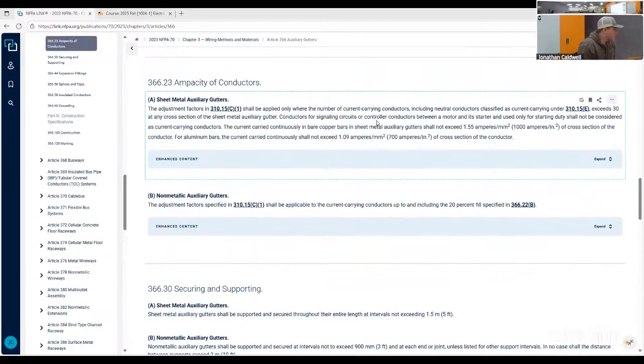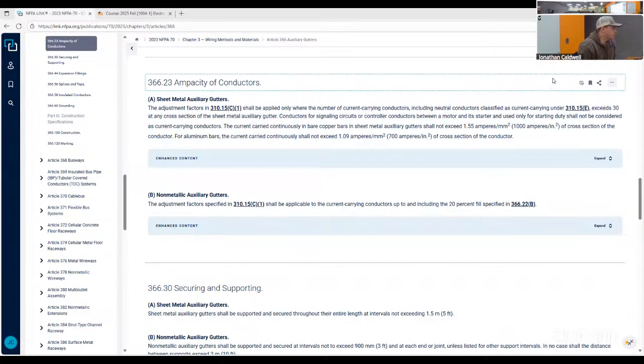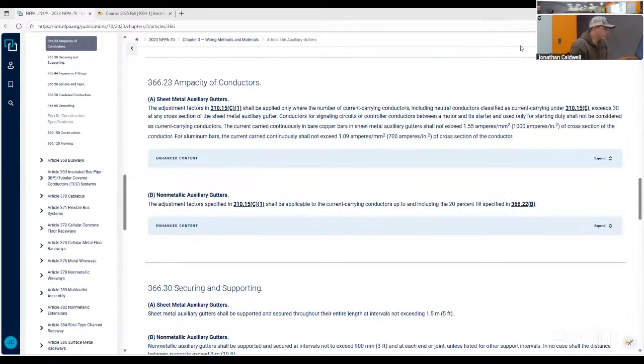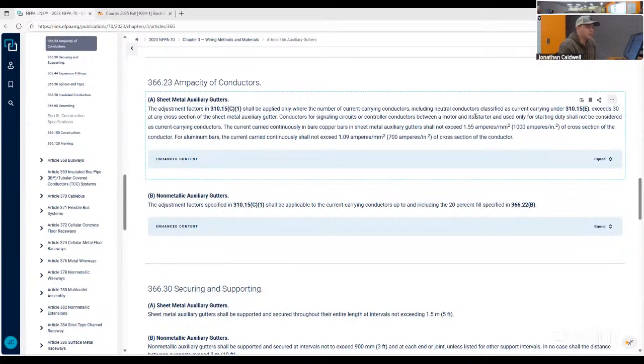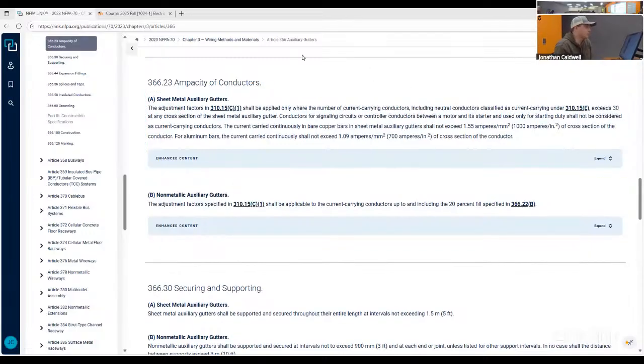So the adjustment factors in 310.15(C)(1) shall be applied only where the number of current carrying conductors, including neutral conductors classified as current carrying, exceeds 30 at any cross section of the sheet metal auxiliary gutter. Conductors for signaling circuits or controller conductors between a motor and its starter and used only for starting duty shall not be considered as current carrying conductors. So just real quick, signal circuits like fire alarm, things like that, and then a starter, a start-stop circuit. There's no other current going through it; the only current is when you push that start button, and that's the only time the current goes through it.